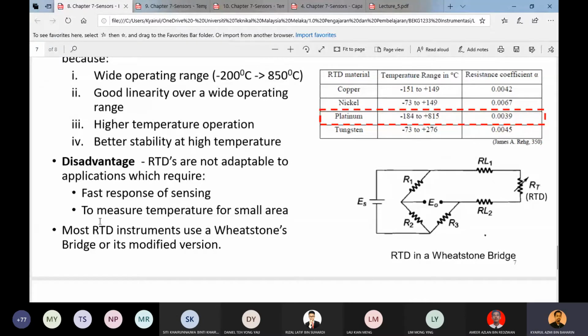Point number two: RTD is not suitable for measuring temperature in a small area. Say you want to measure the temperature on a motherboard, like in a PC or a handphone — the area is quite compact. RTD can't operate well in such tight or small spaces, so we need to use other types of sensors, which we'll see afterwards. These are the two main disadvantages of RTDs.